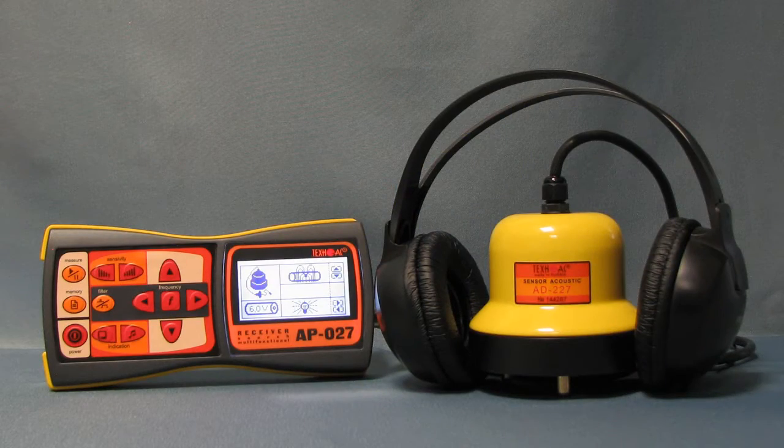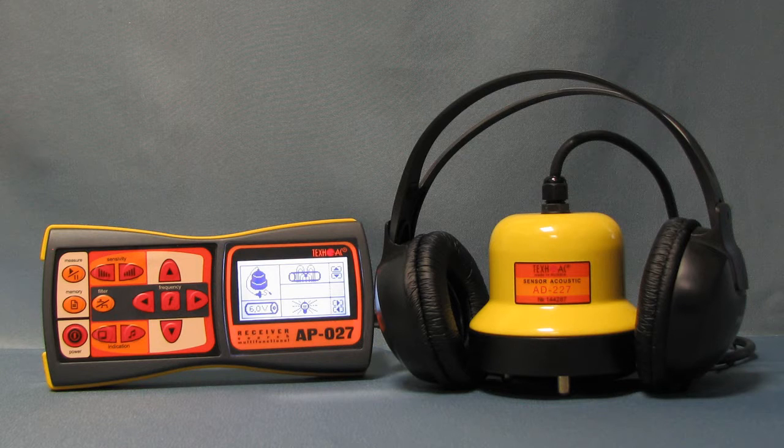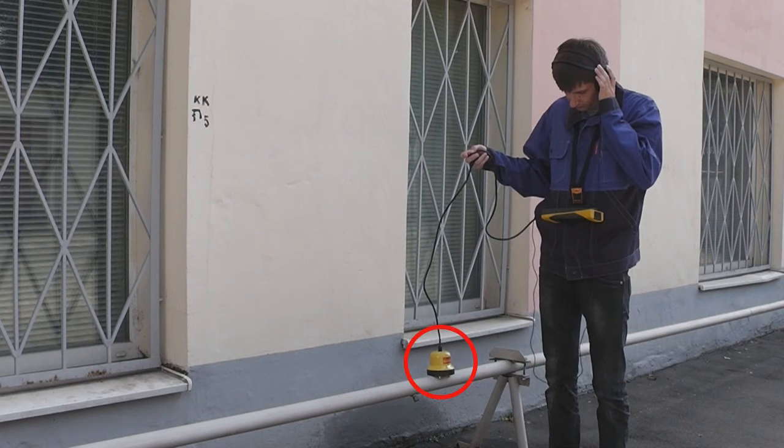AP-027 in leak detection mode is used together with an acoustic sensor and headphones. Beforehand, it is advised to perform the tracing of the pipeline and isolate the supposedly damaged area by closing the gate valves. It is also advised to place the acoustic sensor on the pipe and hear the leakage in order to recognize the same sound while walking on the ground.